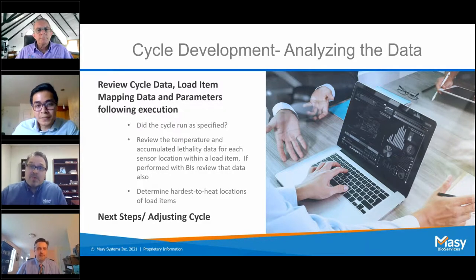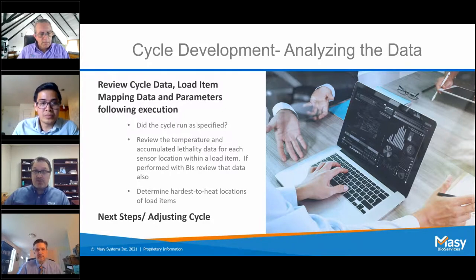Yes, so obviously, the cycle data is really important. It's important to look at it once you have finished your runs, and you want to assess that data to see if your cycle performed as you expected it to. If all of your parameters gave you good results, for example, if you're looking for equilibration, if you're trying to meet that tight European spec, did you get there? Are you close? You may need to increase your vacuum pulses, for example, if you're not quite getting the result that you want.